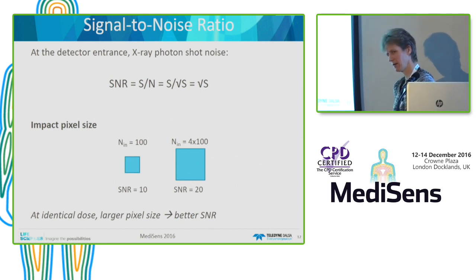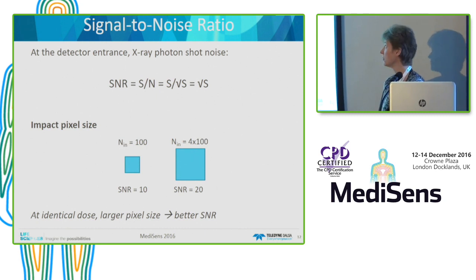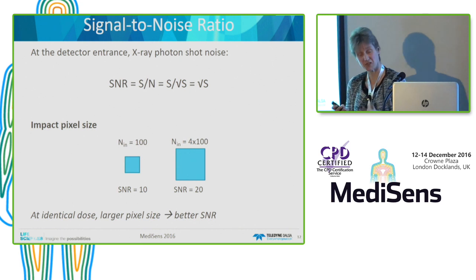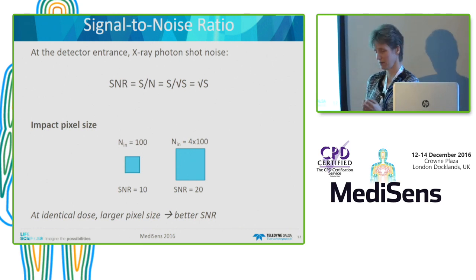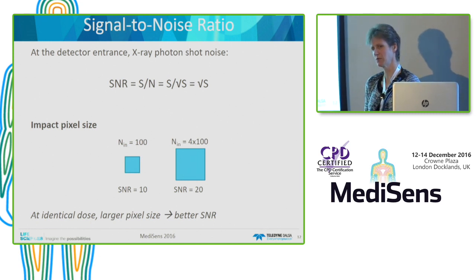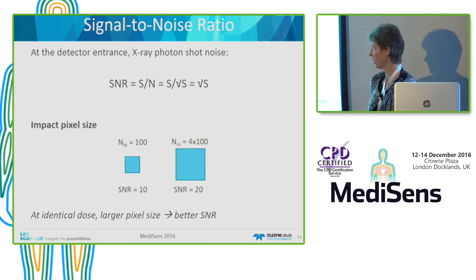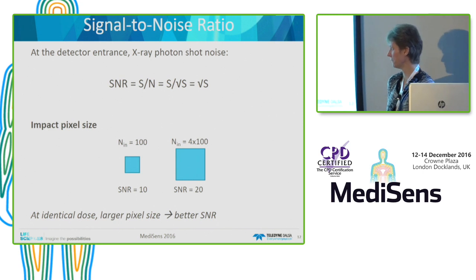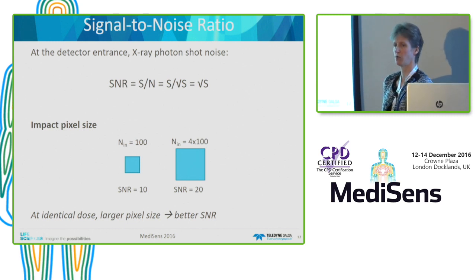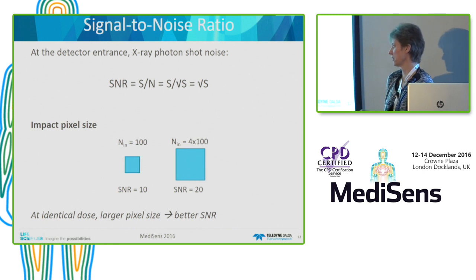Another aspect of image quality is the signal-to-noise ratio. Taking the statistical photon shot noise into account, the SNR of the incoming image on your detector is the square root of the signal. This means that if we change the pixel size, the SNR will change as well. For a small pixel where 100 photons come in, the SNR will be 10. If we bin or make the pixel twice as large in both directions, four times more photons come in, and the SNR will be 20. So at identical dose, the expectation is that the larger the pixel size, the better the SNR performance.